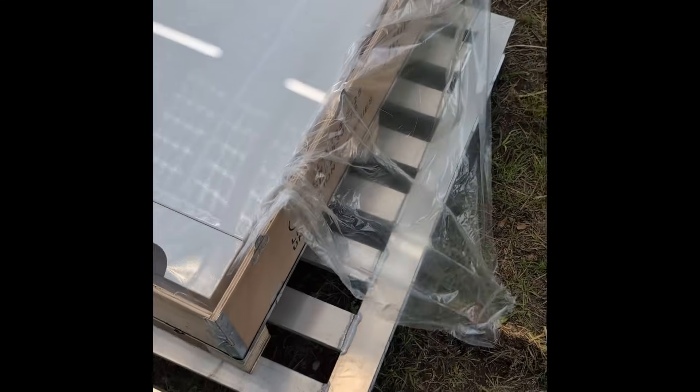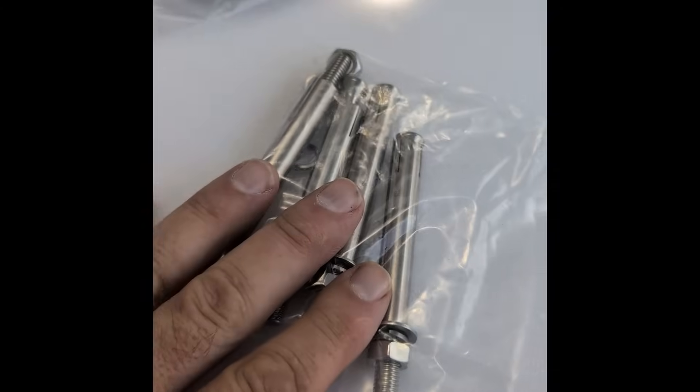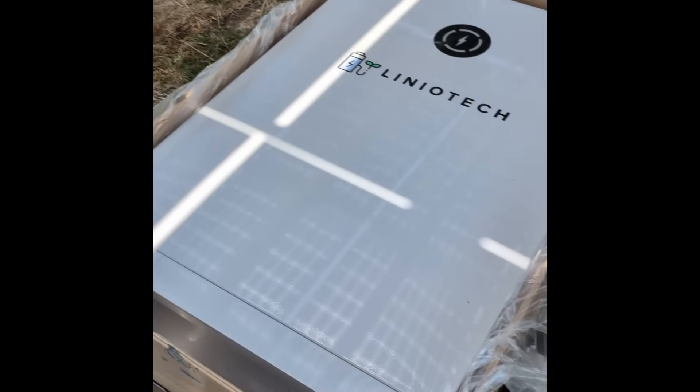You can just keep paralleling them up. These all come with a master-slave configuration. They come with comms cables for your BMS, typical grounding, wedge anchors to mount it to your concrete floor, and Amphenol-style connectors for the battery cables — positive and negative. Very nice.